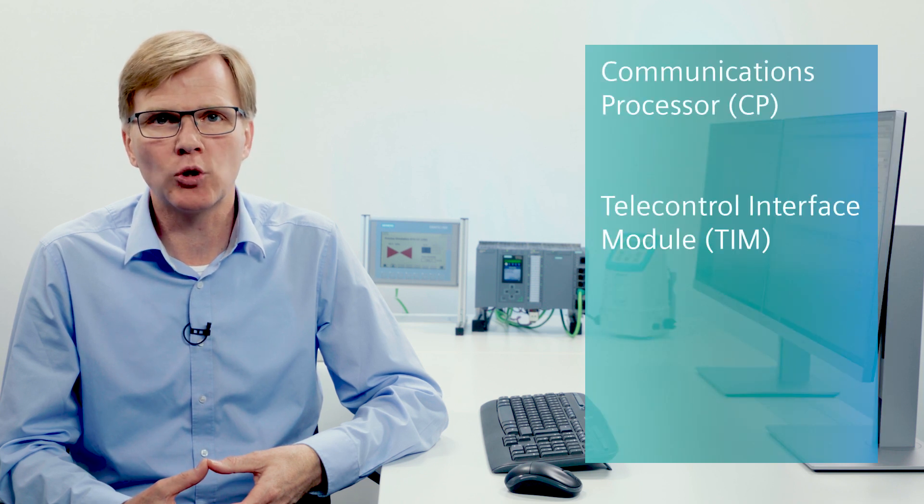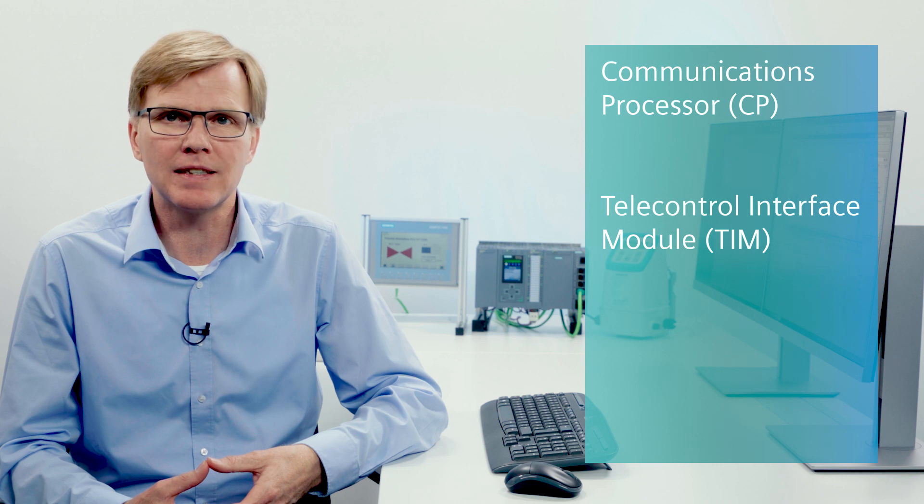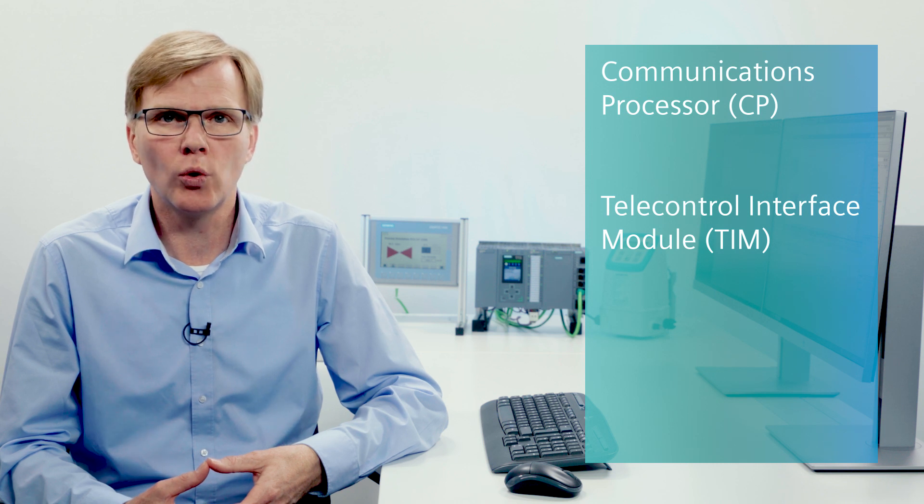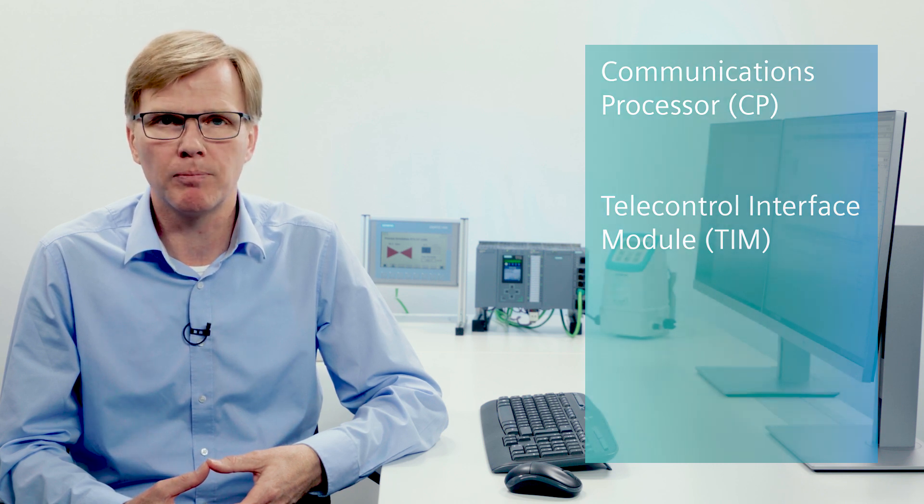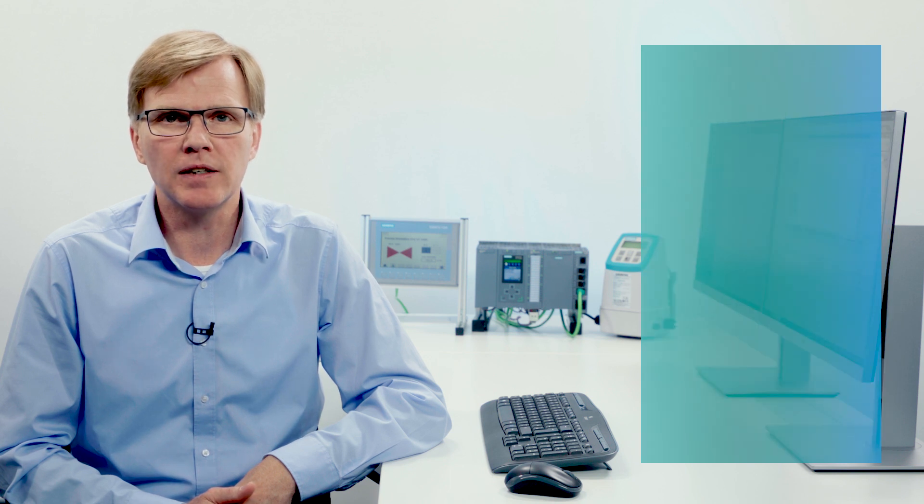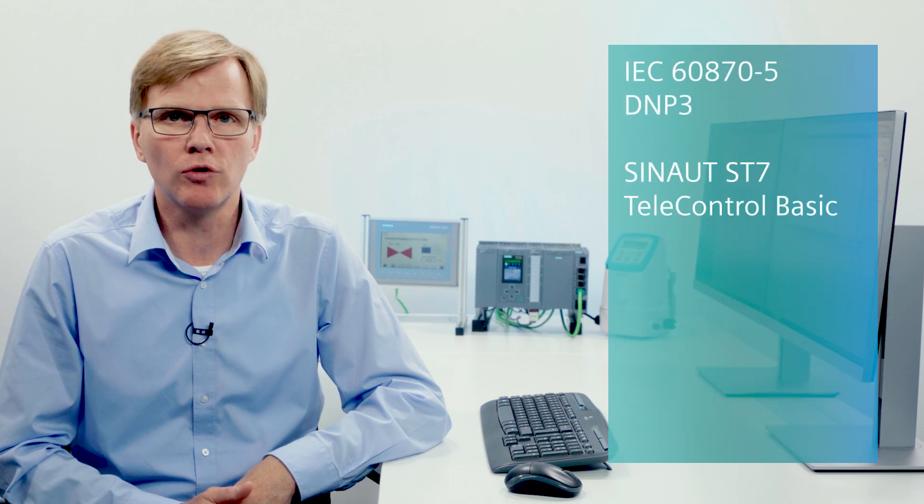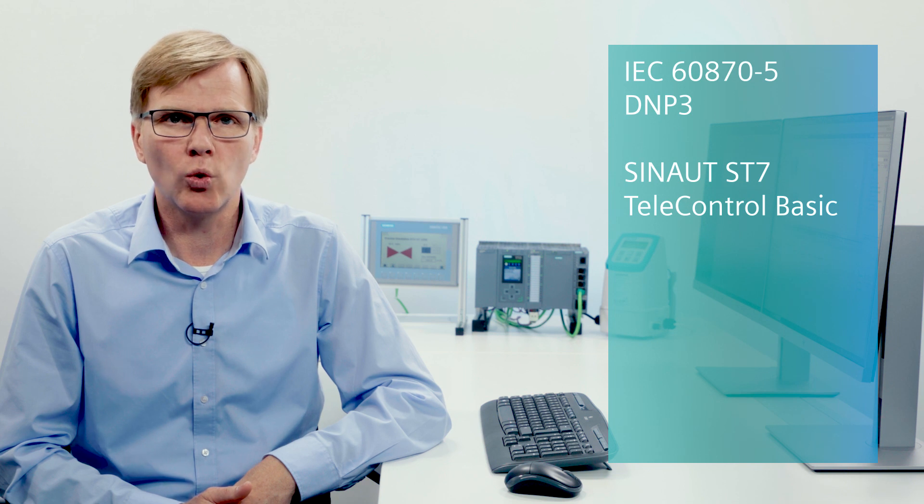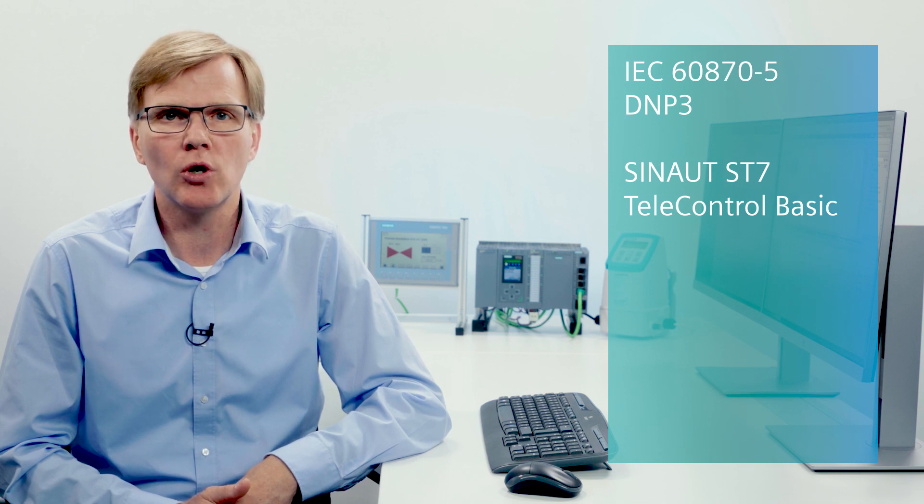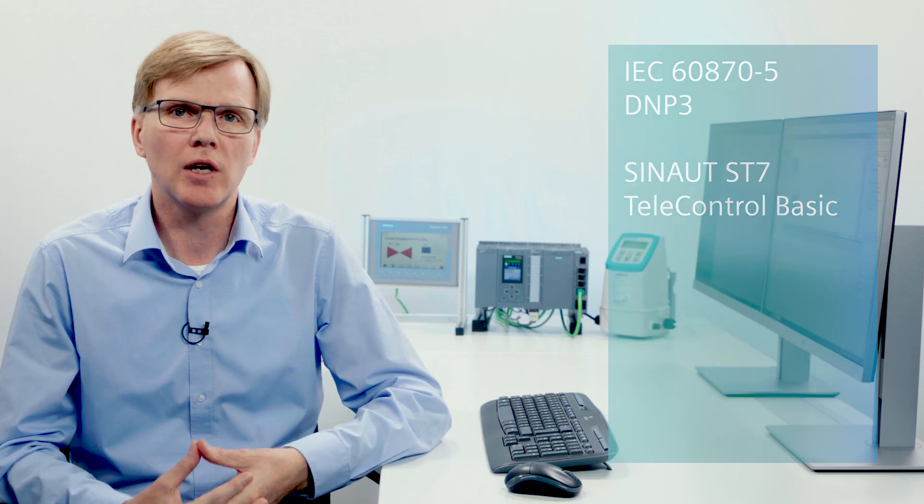I will now show you how to set up a modular RTU based on a SIMATIC S7 controller. This can be accomplished either with a communications processor or a telecontrol interface module. Thanks to their multi-protocol capability, you can choose between the following well-known and widespread telecontrol protocols: IEC 60870-5, DNP3, or the Siemens protocols SINAUT ST7 or Telecontrol BASIC. You can thus set up a PLC-based modular RTU based on the SIMATIC S7-1200 or the S7-1500 or even with the distributed controller ET200SP.